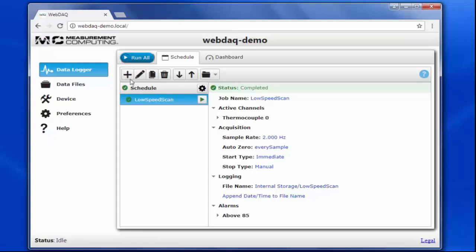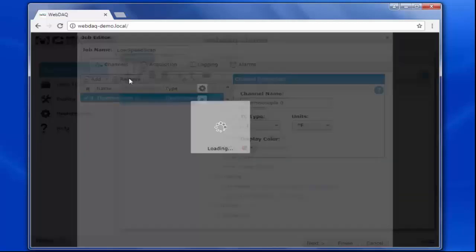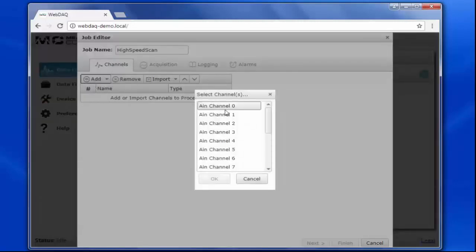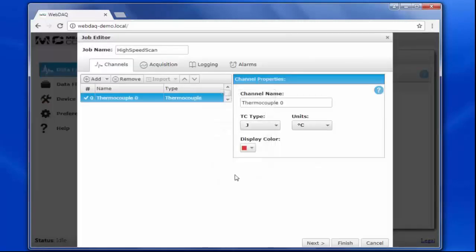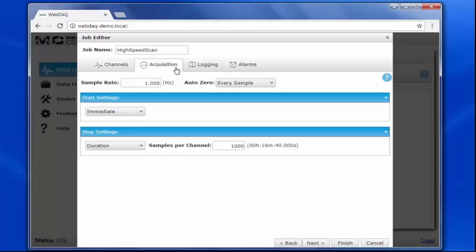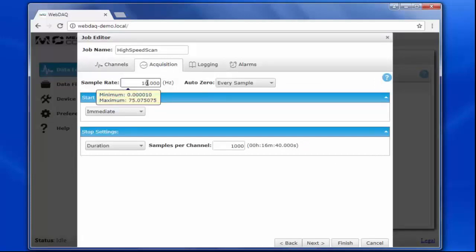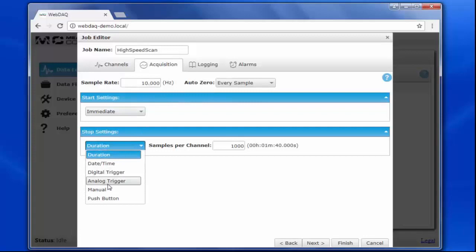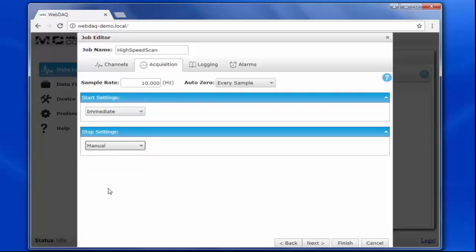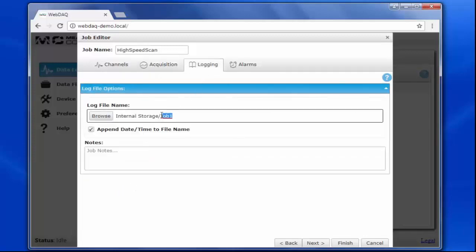Let's take a look at how I can set this up. For my high-speed acquisition task, I'll create a second job and name it High Speed Scan. I'm still using the same thermocouple, so it's type J in degrees Fahrenheit. In the acquisition settings, I'll change the sample rate to 10 Hz and keep the same start and stop conditions as the first job. For the logging options, we'll log this data to the internal storage with a log file name of High Speed Scan plus the appended date and time.